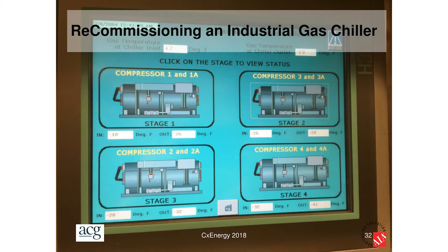Here's a screenshot of the HMI, the human machine interface on the control panel. You'll notice right here it's entering the system at 7 degrees. Then there's a little bit of residual cooling as it goes through that first economizer heat exchanger. It enters the first compressor at 10 below and exits at 26 below. It enters the next one at 26 below and goes to 28 below, then 28 below to 32 below, and then 32, in this case, to 41 below.